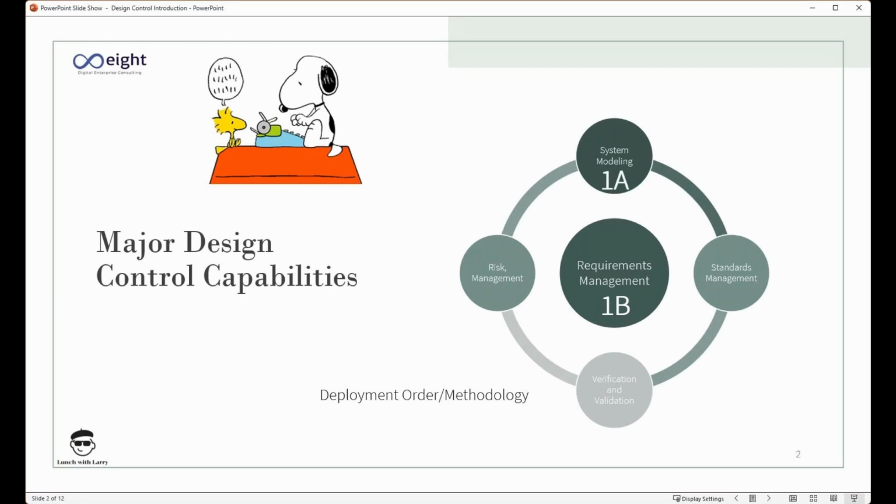One of the things I found as we deployed across a variety of different divisions is that most people don't have a really clear understanding of product function. It's not that they struggle to understand how a femto laser works, or how a surgical handpiece works, but rather how to construct an understanding of the performance of the device in a formal way. How do we develop a set of functional diagrams that inform what the requirements management should be?